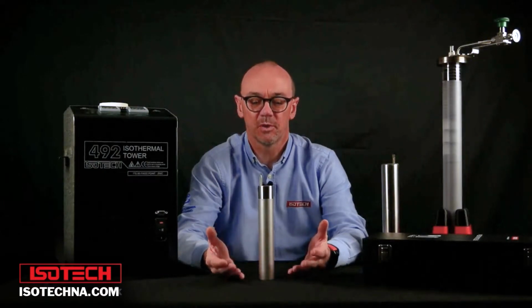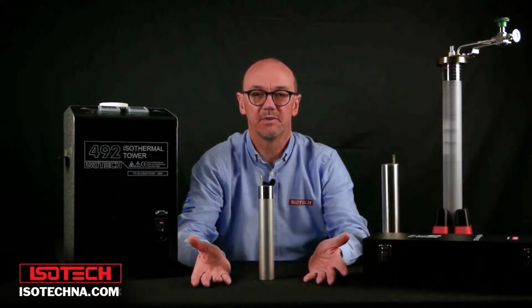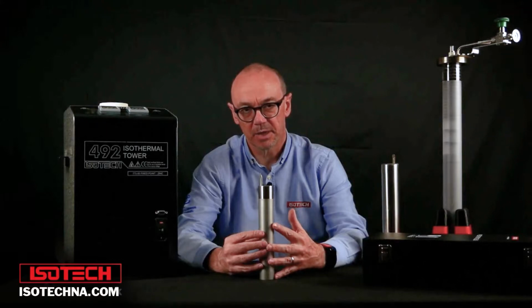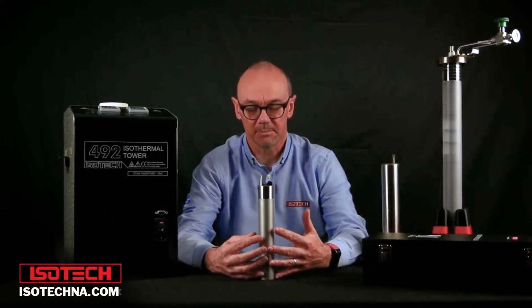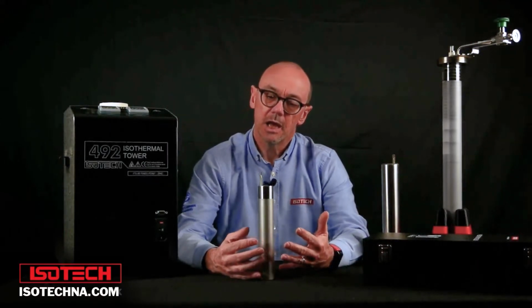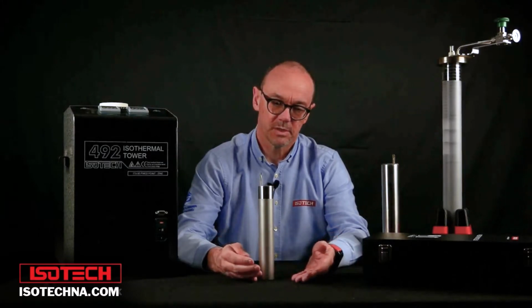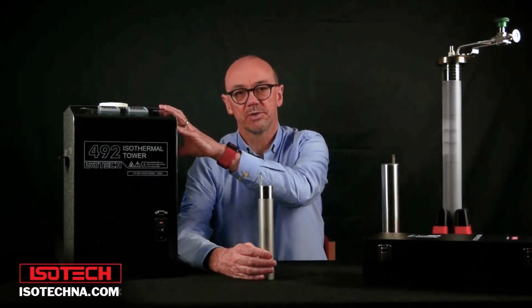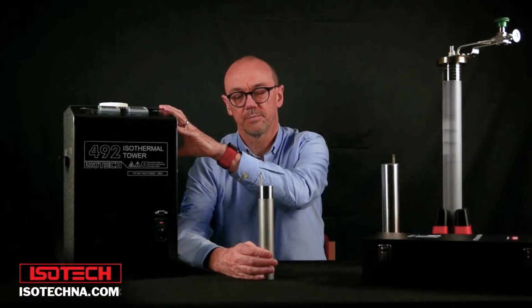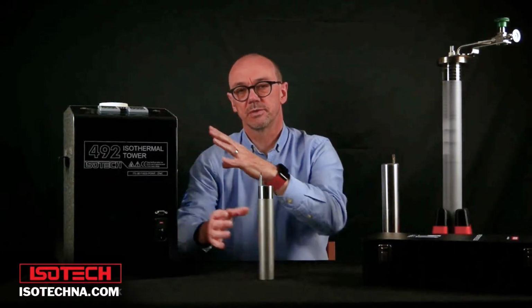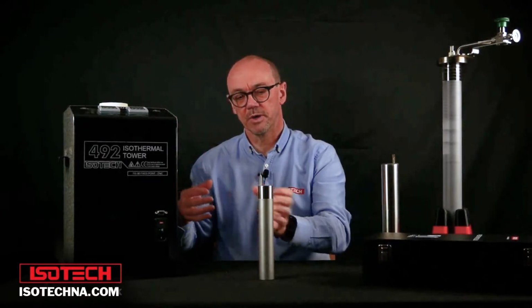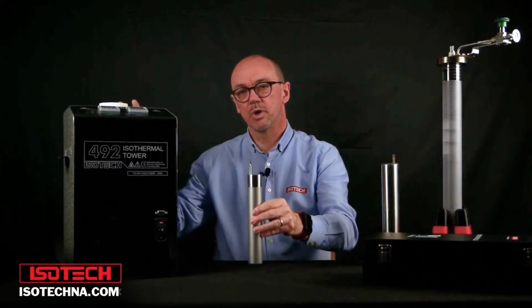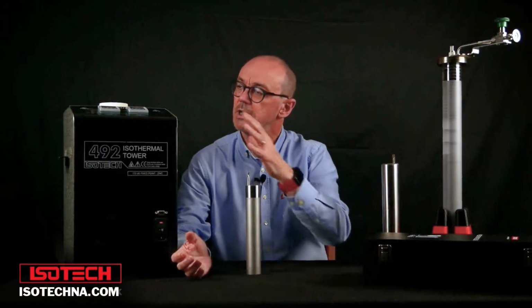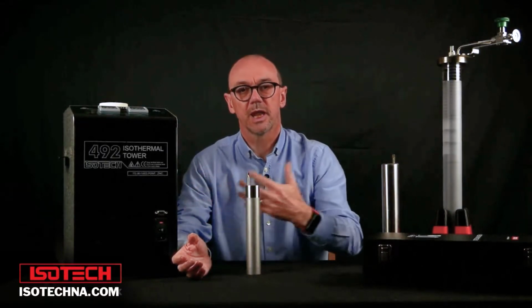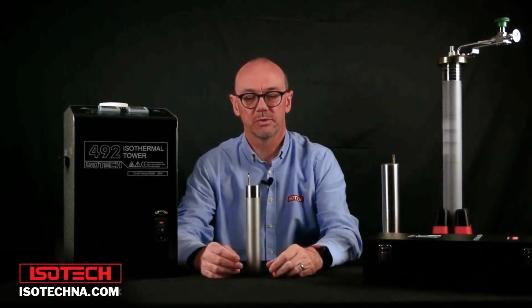So as I mentioned, there are quite a few different types of ITS 90 fixed point cell. This is a metal clad cell, and we call it a slim cell, and we use that in some apparatus. This is a product from ISOTECH called the ISO tower, and this product combines a heat pipe and the furnace with the cell into one integrated device, and we can use the ISO tower as a standalone system to calibrate at the ITS 90 fixed points.